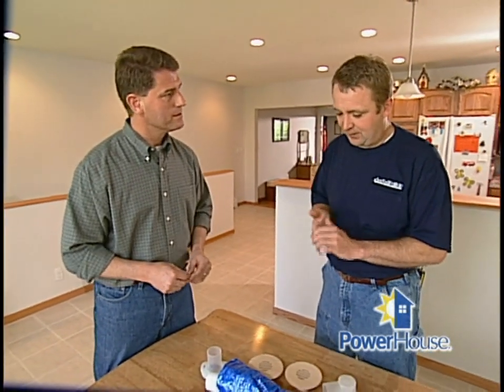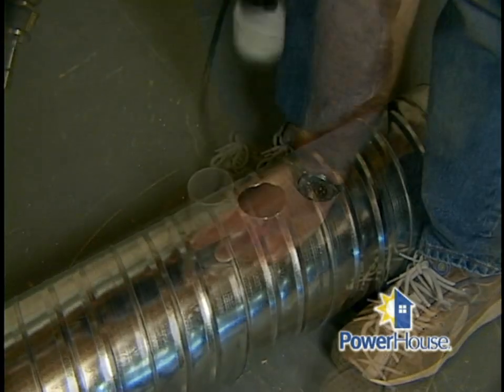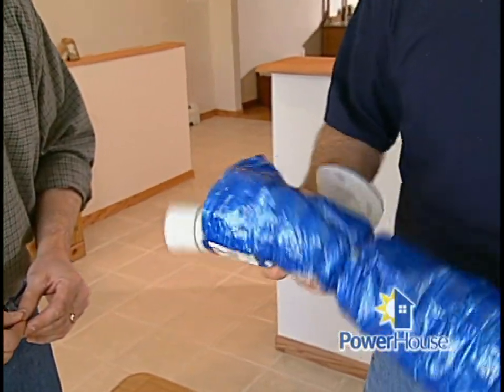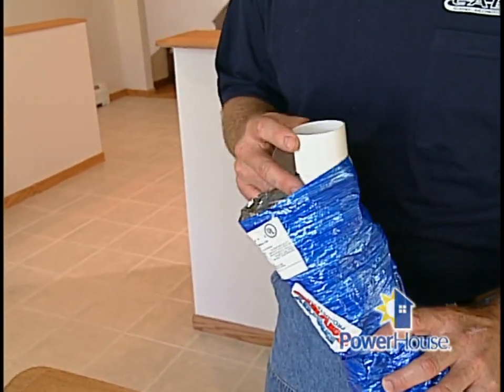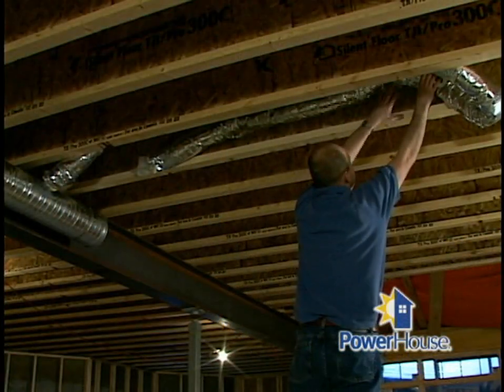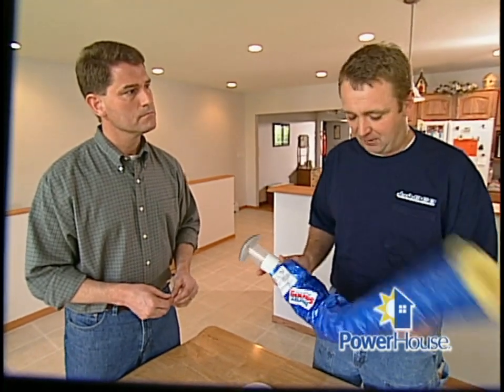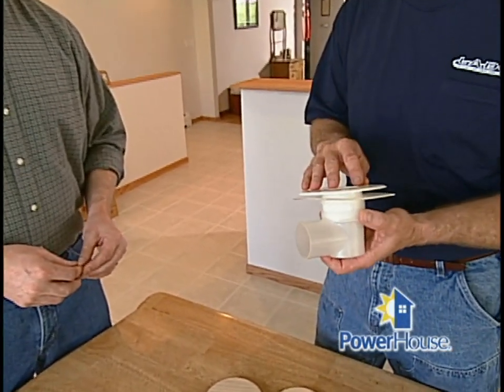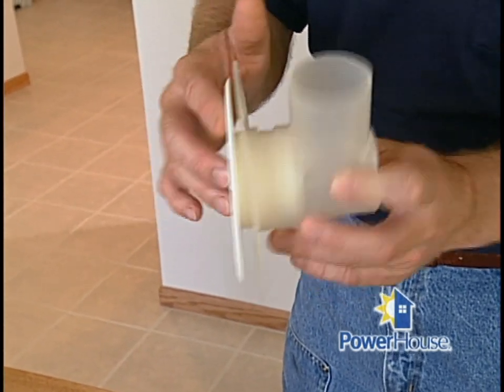Tell us about installation — how does that work? The installation process is fairly simple, and this is where the labor savings come in. If we have an eight-inch trunk line running in the attic, we have this fitting we call our takeoff, which is mounted to the side of the main trunk line. We have this insulated two-inch supply pipe with a foiled-back covering for efficiency, retaining our conditioned air within the pipe. We run it over to the diffuser and hook it up. There's a minimum ten-foot run length required for sound attenuation, because we want this system to be quiet. The diffuser also has a damper to control the sound and noise coming from the register.